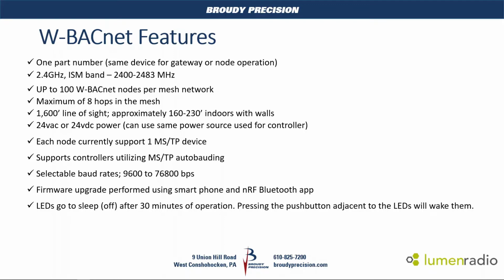It can be powered from a 24 volt AC or DC source, and you can use the same power that's fed to the controller. At this point, each node can support up to one and only one MSTP device. In future releases, there is a possibility that you'll be able to go to maybe 3 or 4 devices per node, but at this point it's one device per node.